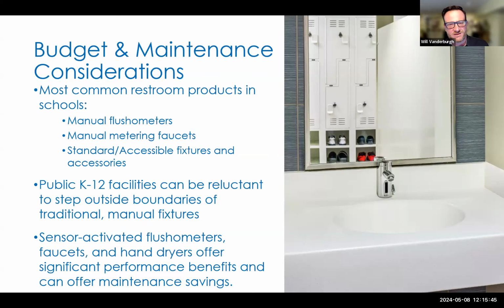What's interesting, though, is that being mechanical devices, they're quite prone to failure before some of the newer technologies, particularly sensor-activated flush valves. If you've seen the abuse that most flush valves take in public settings, where they're typically kicked on the handle, which over time can pull that mounting bracket loose from the wall, causing damage there. And then the faucets, likewise, being mechanical and spring loaded, they're prone to failing much more frequently than a sensor activated faucet would be.